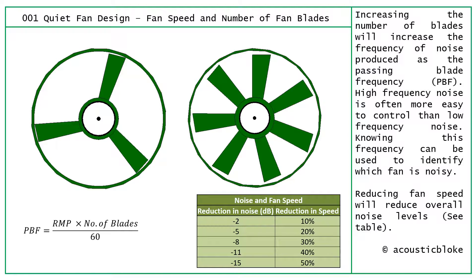The blade passing frequency is calculated by taking the RPM — the speed of the fan — multiplying that by the number of blades, and then dividing by 60. By adding more blades we shift the frequency from low to higher; by removing blades the frequency goes down.